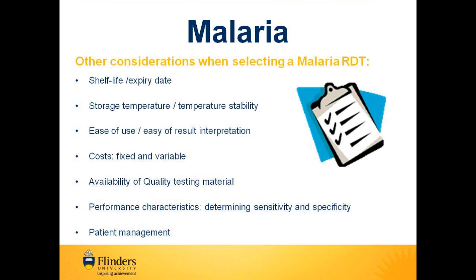When selecting a malaria RDT, other things that need to be considered are the shelf life or expiry date, which should ideally be 18 months or more. The storage temperature and temperature stability, which should ideally be up to 40 degrees Celsius, to ensure safe transport of RDTs is possible. The ease of use and interpretation of results, and also the cost of the RDT, its delivery and any other materials or consumables needed to conduct testing should be considered. Although some RDTs may be cheaper than others, they may require additional equipment such as lancets or capillaries that will increase the cost per test. Some manufacturers will have their own quality testing materials available to support field testing, but if they do not supply quality testing material, then it will have to be sourced elsewhere and trialled for its compatibility with the RDT.